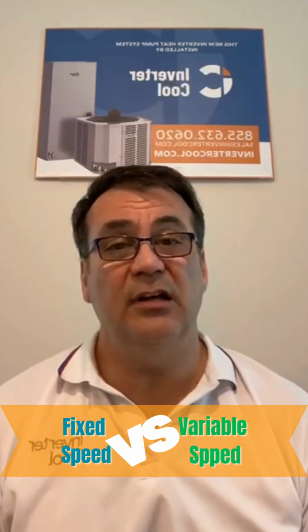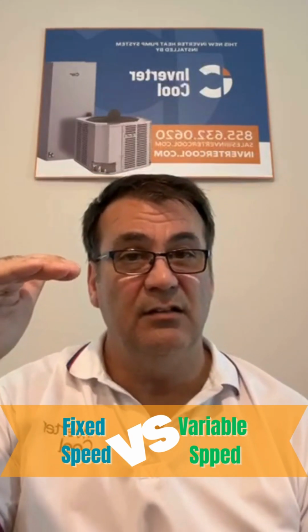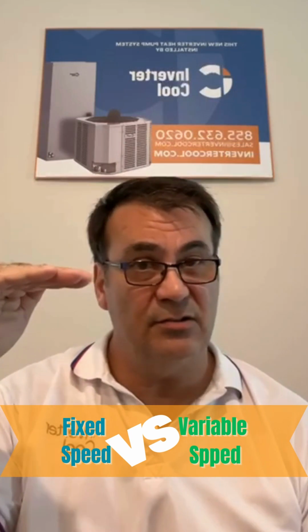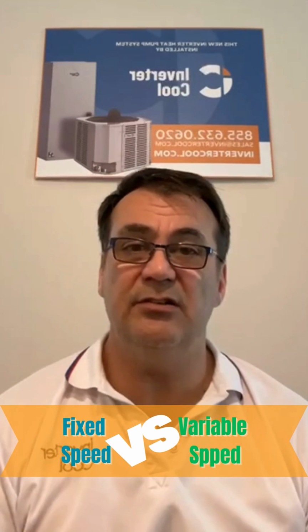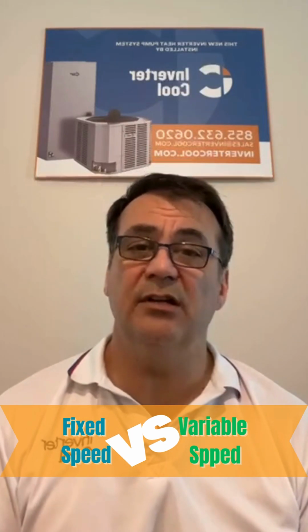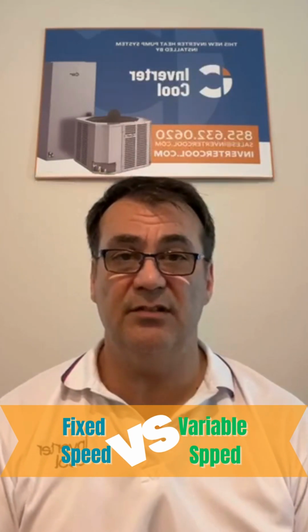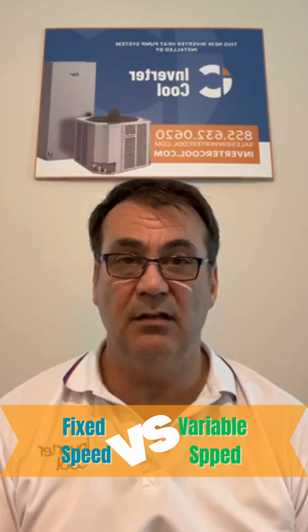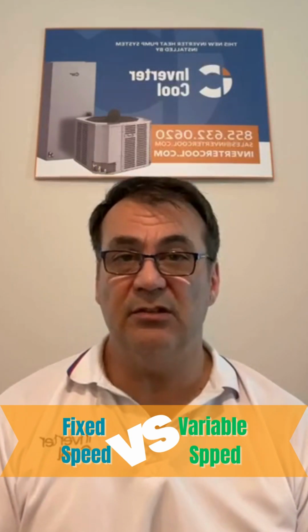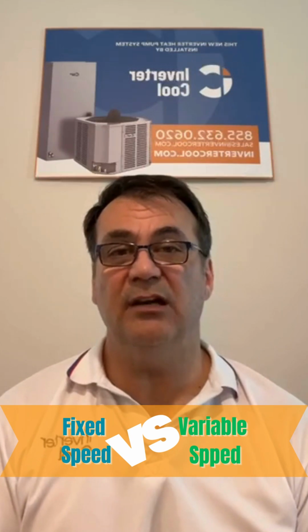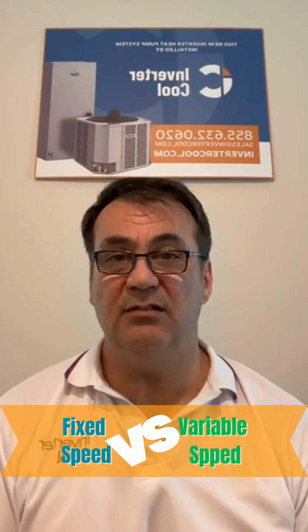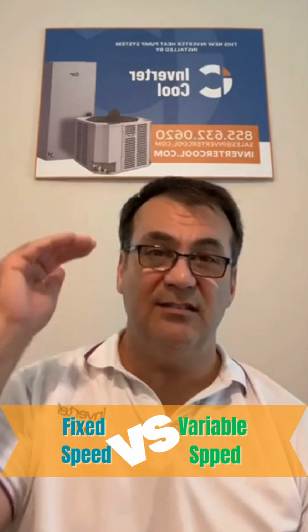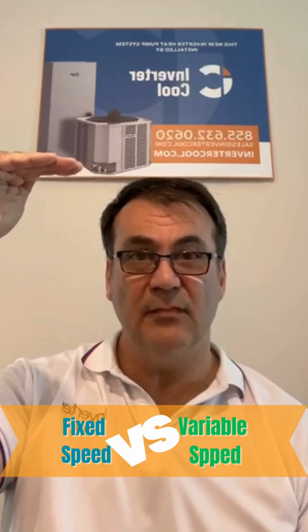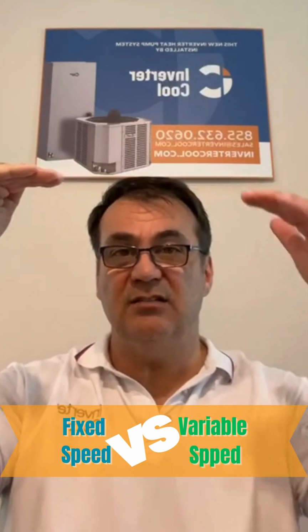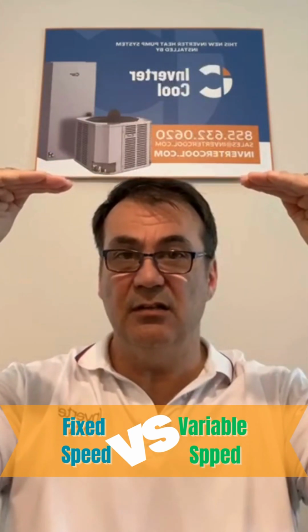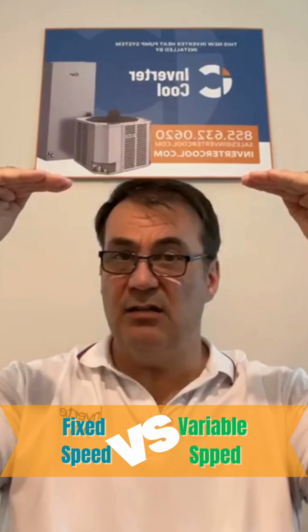So if it's running at a partial capacity, the SEER rating is actually not a true indication of how much energy you're saving, because when it's running at that partial capacity, the efficiency is increased. Units are measured for efficiency running at 100% speed. So if you have a fixed speed 16 SEER2 system and an inverter system that's also 16 SEER2, the energy usage is not going to be equal.